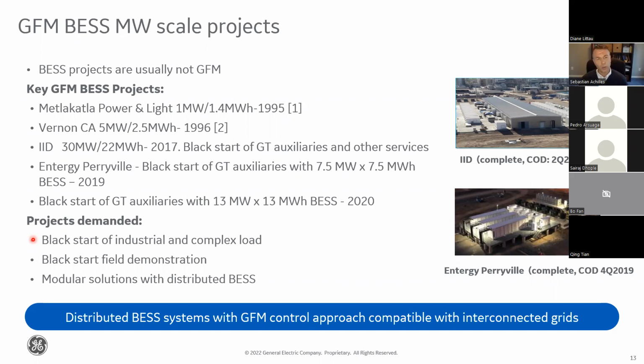All of them were deployed with modular solutions and distributed batteries, in the sense that you have several, let's say 10, 15, 30 converters that operate individually and independently, performing the grid forming controls to achieve full plant black starting. That is related to what we expect to see in interconnected systems, where you have more than a single inverter performing the grid forming features.